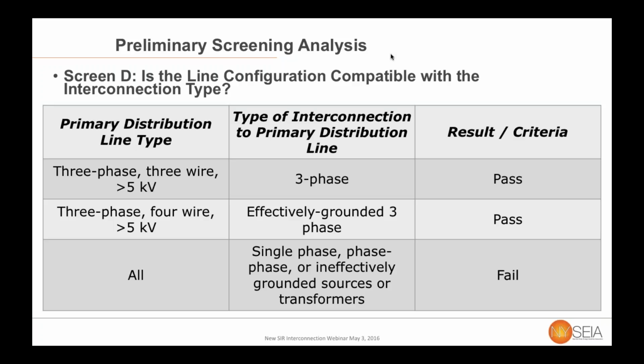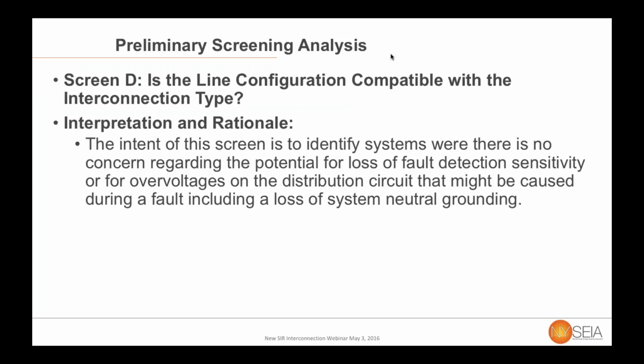If you have a three-phase, four-wire system, so you have a grounded system, then you must interconnect with an effectively grounded three-phase system in order to pass. For all of these systems, interconnecting on single phase, phase-to-phase, or ineffectively grounded sources would cause you to fail. And this is one of those places where we have a question that we're going to work to clarify some of this language. I'll speak of that in a second.